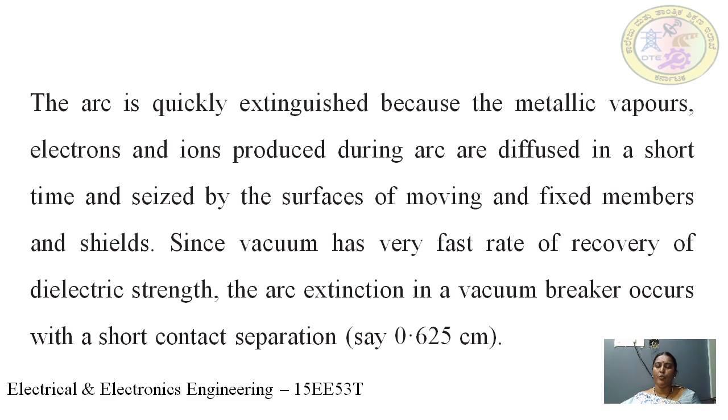Since vacuum has a very fast rate of recovery of dielectric strength, the arc extinction in a vacuum breaker occurs with a short contact separation, say about 0.625 centimeter.